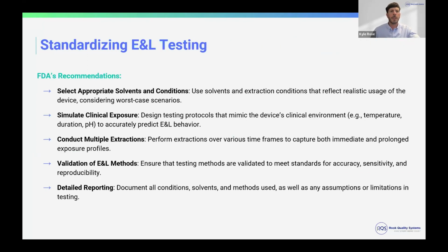So with the standardization of this extractable and leachable testing, the FDA has a few different recommendations. So first is selecting appropriate solvents and conditions. So using solvents and extraction conditions that reflect realistic usage of the device, considering worst case scenarios. Within the guidance, they provide different types of solvents you can use, polar, non-polar, different types of alcohol or mixtures you can use as well. So you really need to look at your device, look at how it's being used, and then determine the best path for your testing relative to the solvents.